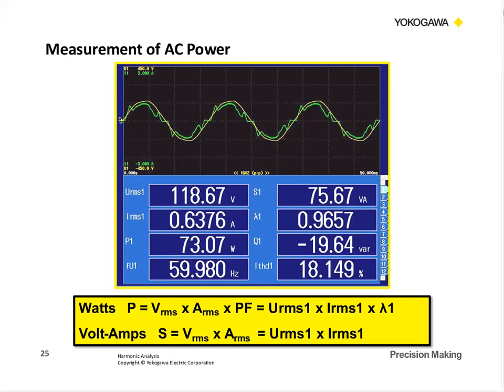Here's an example. This is a power supply. It had a lot of noise on the current. Voltage was fairly clean. So if we look at the RMS voltage there, at 118.67 volts and a current of 0.6376, we multiply those together, we get the VA, 75.67. And then our power, our watts, is 73.07. And lambda is a universal symbol for power factor. So the power factor was 0.9657. So if we take the VA times the power factor, we should come out with the wattage there. And we're showing one additional function. We've got the frequency of the waveform, and we're showing, in this case, the current total harmonic distortion. So we can measure these simultaneously with the harmonics as well as all the normal measurement functions. So it's just an example of some of our measurements.